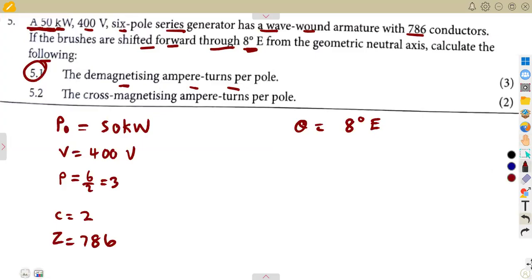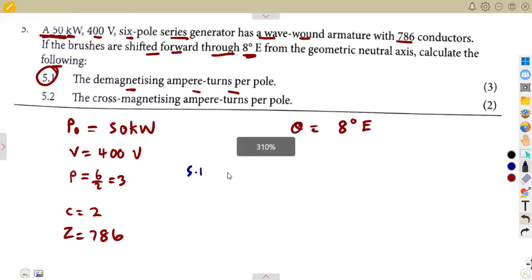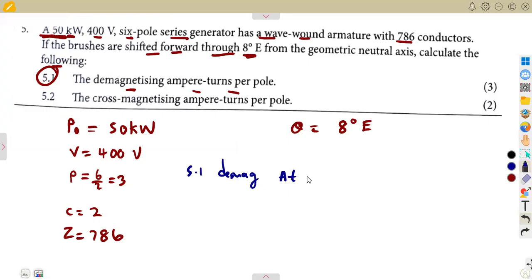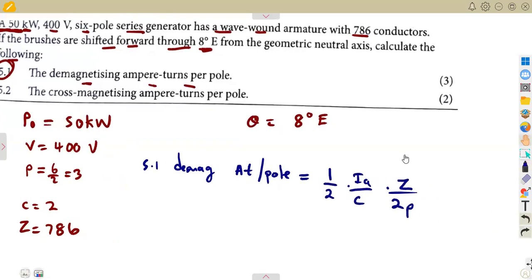To calculate the demagnetizing ampere-turns per pole, the formula is: one-half times the armature current over C, times Z over 2P. That gives you the total ampere-turns per pole. For the demagnetizing component specifically, you multiply by four-theta over 360 degrees, where theta must be in electrical degrees.